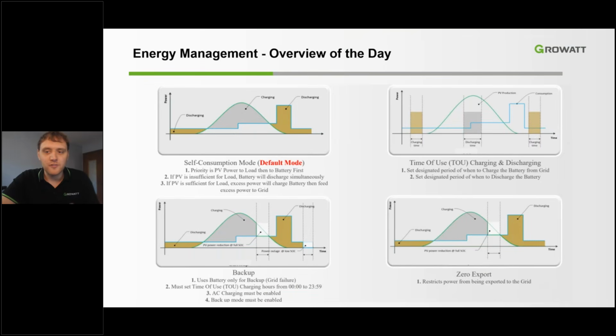So here we can see the bell curve of many different ESS modes of the inverter. The self-consumption mode is set by default, and the customer loads are prioritizing PV energy first, then charges the battery with the clipped solar energy. The time of use function is programmed to capture the best rates for energy exportation, prioritizing the load first and reserving energy storage to export to the grid at later times. Again, this is fully configurable, but I would recommend to send energy to the grid during those peak export rates and then maintain that reserve for self-consumption during the night. Zero export can be configured to restrict all power backfed to the grid, and multiple backup modes can be enabled to ensure the customer is ready to back up their home loads when a grid outage occurs.